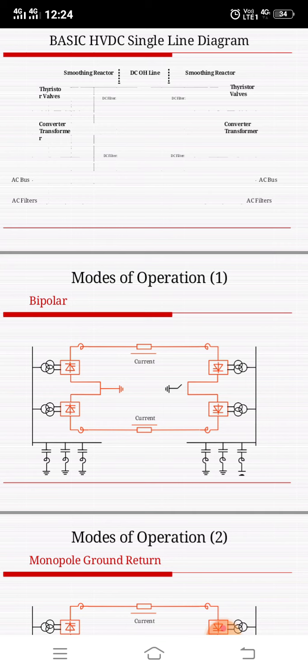The second type is bipolar with a dedicated metallic return path for monopolar operation. If there are restrictions on even temporary use of electrodes, or if the transmission distance is relatively short, a dedicated LVDC metallic return conductor can be considered as an alternative to a ground return path with electrodes.